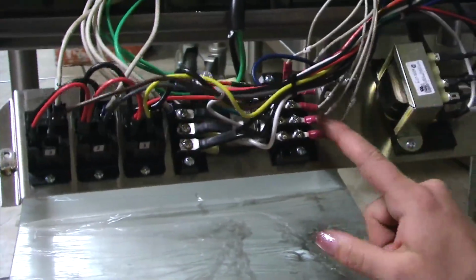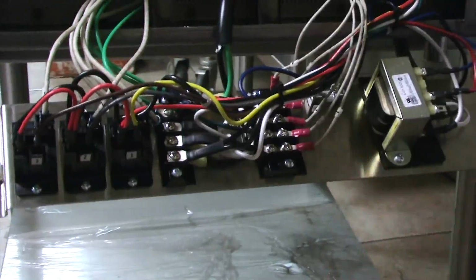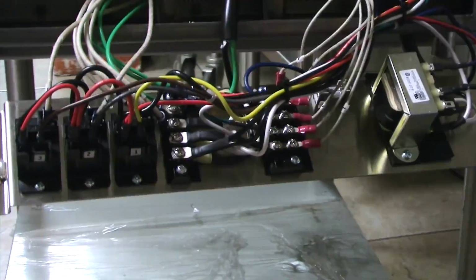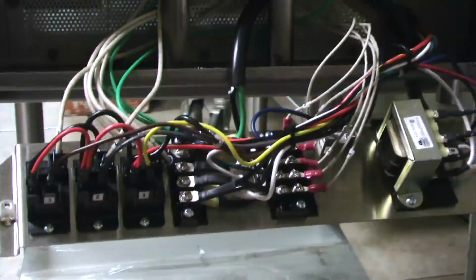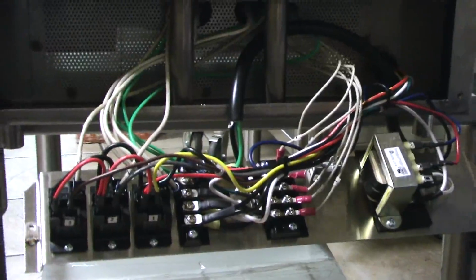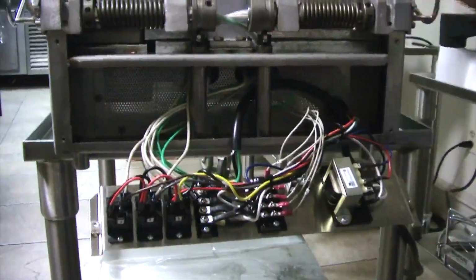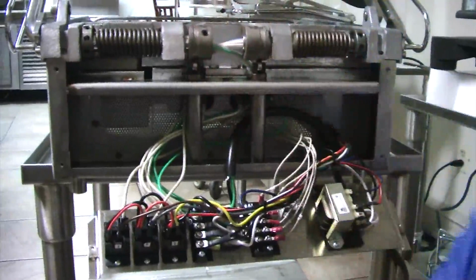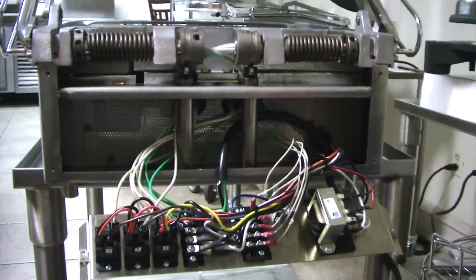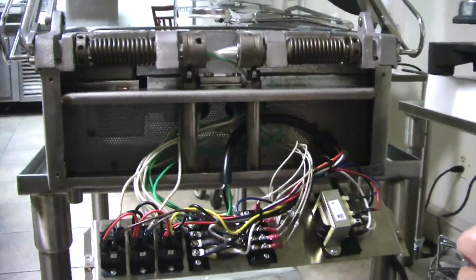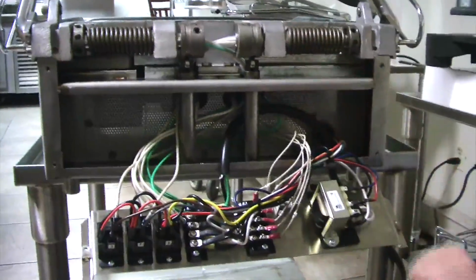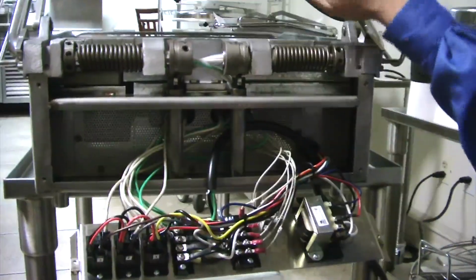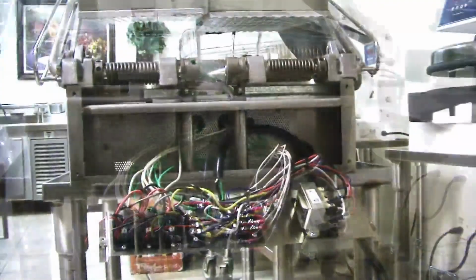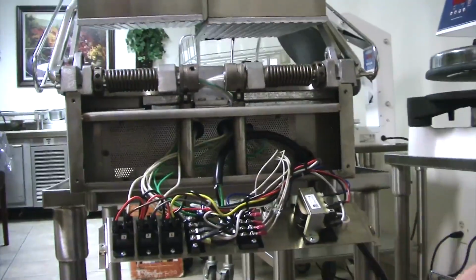Whatever you do, be careful not to switch your wires. When you switch your wires, let's say you checked zone 2 and zone 3 for your sensor wires, and when you plug it all back together and it heats up, your zone 2 will read 450 degrees and your zone 3 will read maybe 590 degrees, and that's because your sensor wires are switched. It's calling for heat because it's not getting it. It thinks it's here, but it's heating here. So this one will overheat as this one will underheat. Definitely make sure that your sensor wires are not crossed, because it will cause that problem.